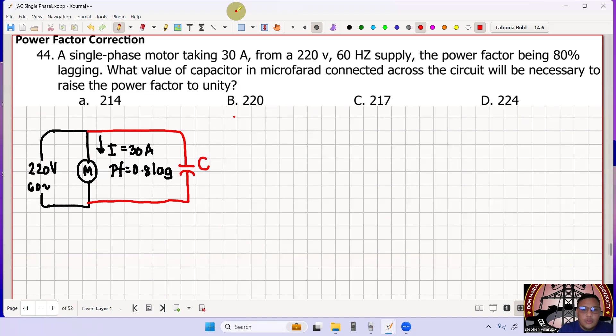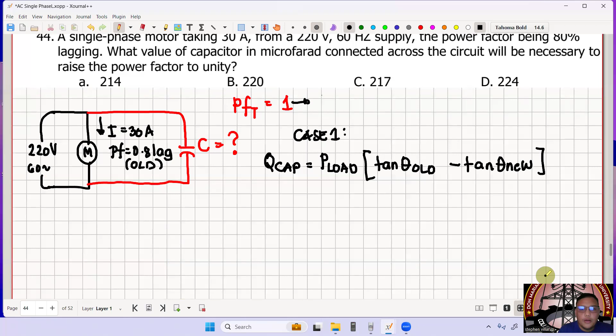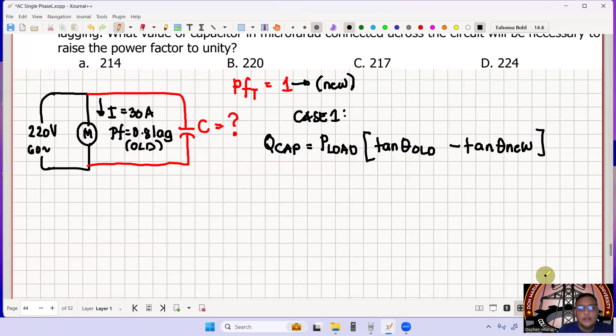Using our case 1 formula, we can solve this. So Q cap, let's get the reactive power of our capacitor. Q cap is equal to P of the load times tangent theta old minus tangent theta new. So our power factor here, this is the old one, 0.8. And this 1 here will become 1 because that's the new power factor.